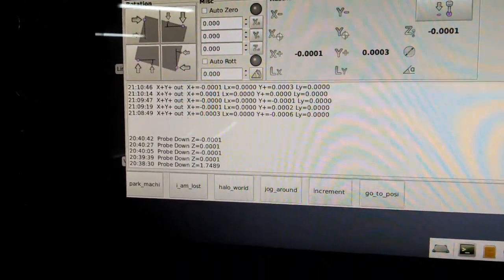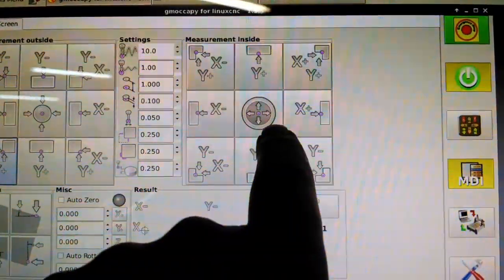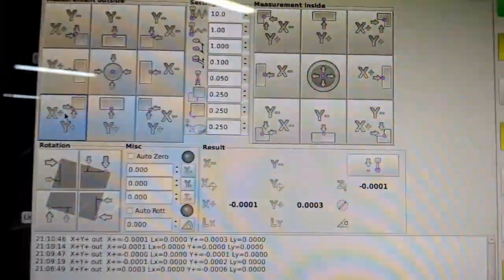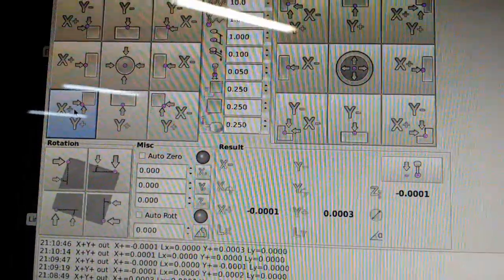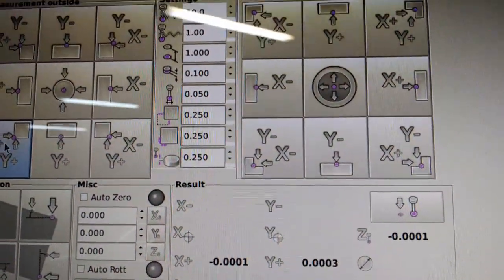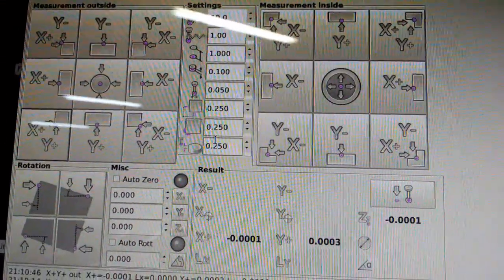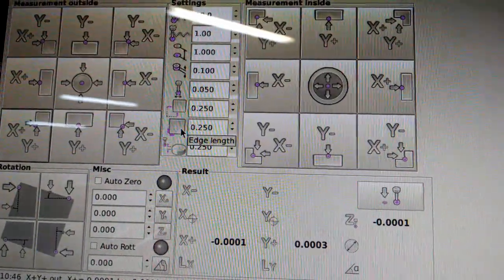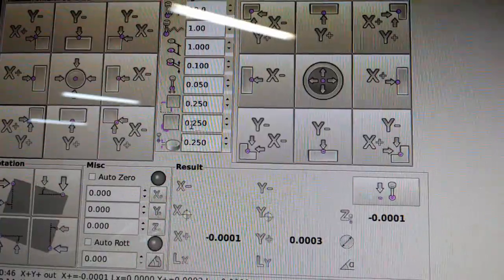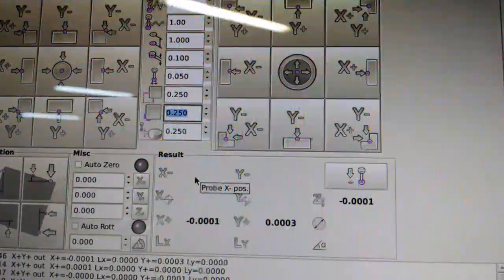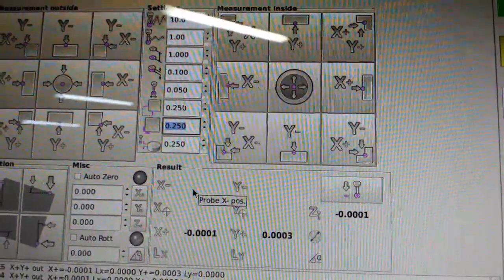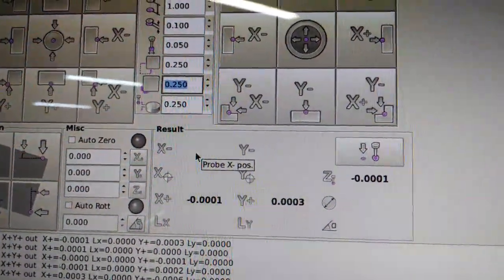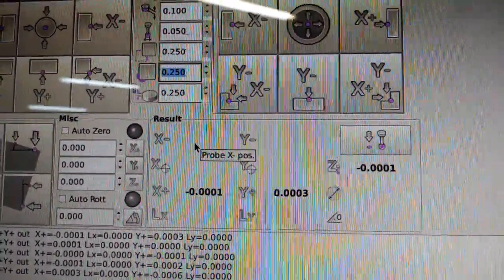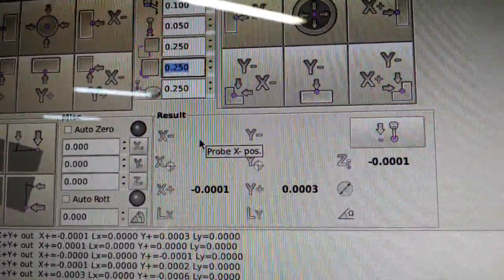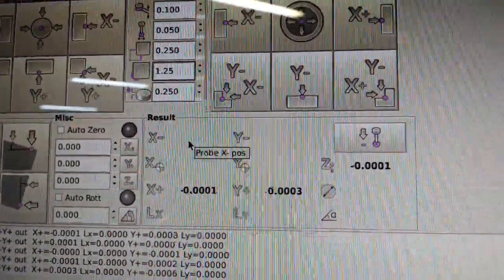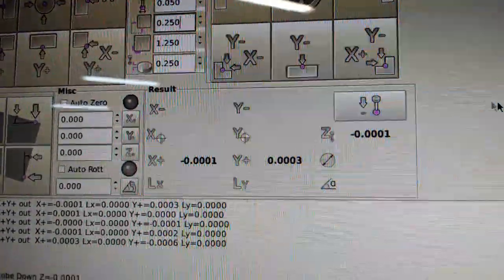So the next thing we're going to do is some probing of an inside of a circle. So we'll use this button here. And what we're going to have to do on that is tweak our dimensions a little bit so that we can probe the circle. The circle that I've got machined is 2 inches exact. So we've got to change the edge length, I believe, is the one we've got to change. So we've got to make that be half the probe diameter, if I recall, or the whole diameter. So we'll actually make it a little bit more than half just to make sure that we get probe contact. So we'll go 1.25, and I'll show you the setup here in a second, and we'll go from there.